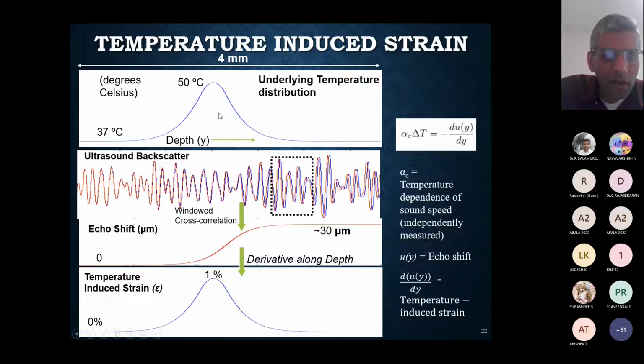What we have is a localized temperature change. Body temperature is 37; this example shows 50 degrees. What you'll see is a very non-uniform effect on the ultrasound echo. This is the portion where the heat is applied, but it's always a cumulative change. If a certain region of tissue is heated, the ultrasound pulse has to go through that heated tissue to reach other portions, so any location beyond the heated tissue also experiences that echo shift.